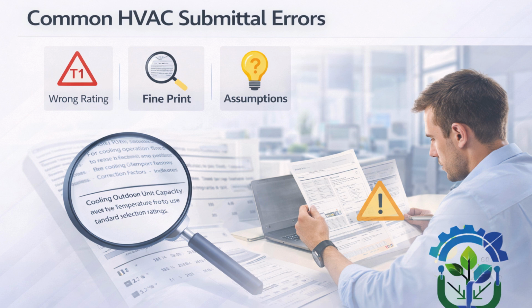As engineers, our responsibility is to check rating conditions carefully, verify actual performance tables, and review compressor operating envelopes. Never ever approve equipment based on model numbers, sales brochures, or marketing claims. Engineering approval must always be based on verified performance data.